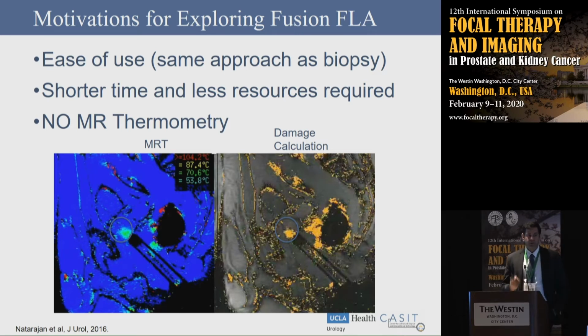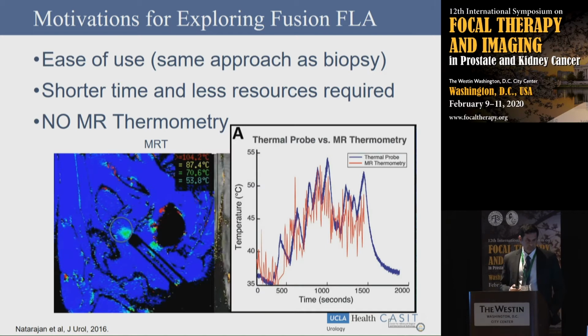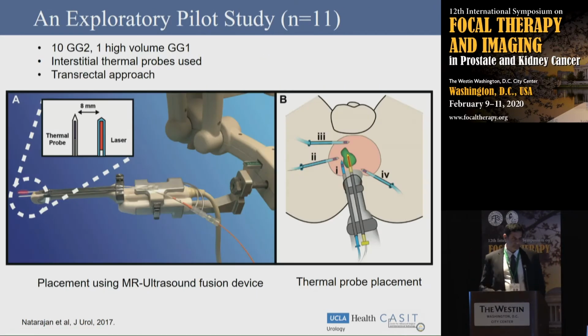MRI thermometry works great if the patient's not moving, if you can have a really accurate idea of what the baseline temperature is, but as soon as the patient starts moving and as the procedure goes on, the thermometry image gets distorted, artifacts appear, and the damage calculation, which is provided by the Visualase software, really is inaccurate. This is a comparison of a direct thermal probe reading versus MRI thermometry, and you can see the increased noise in the signal.